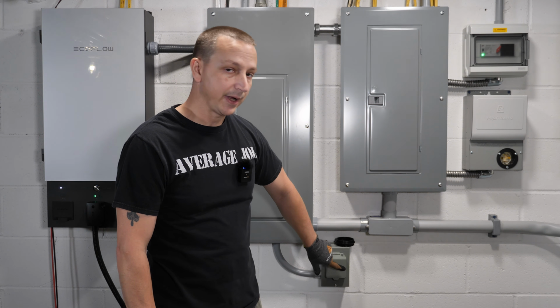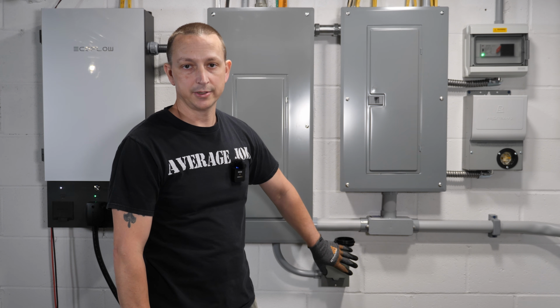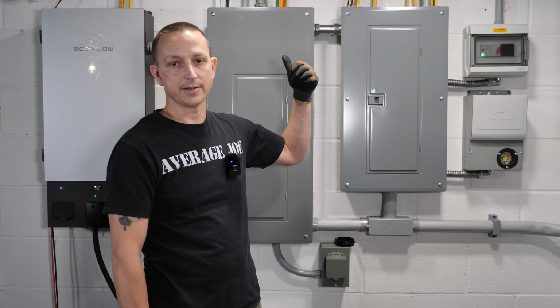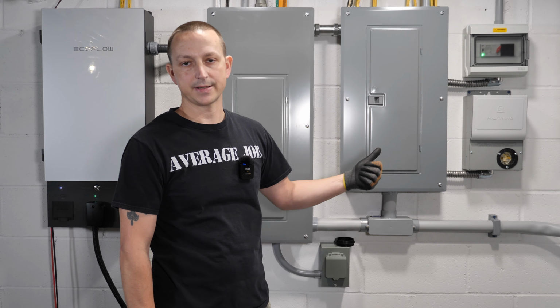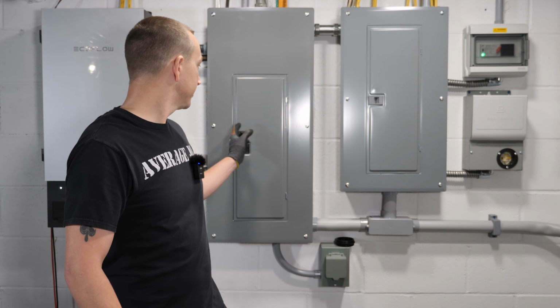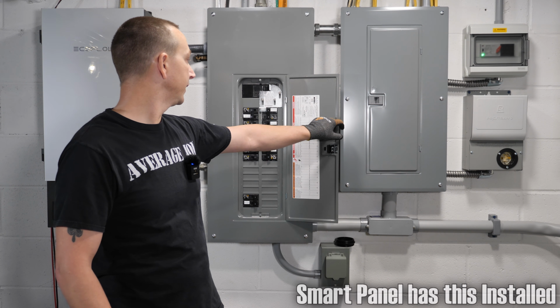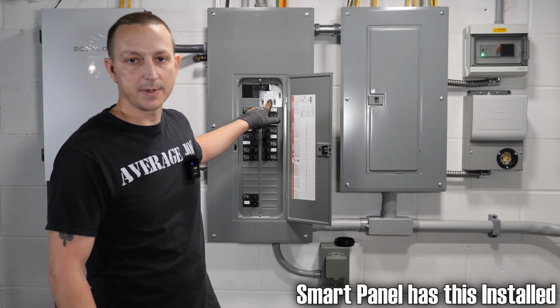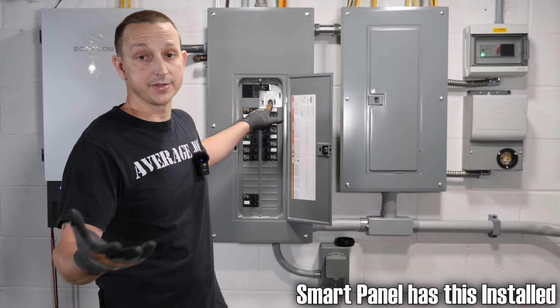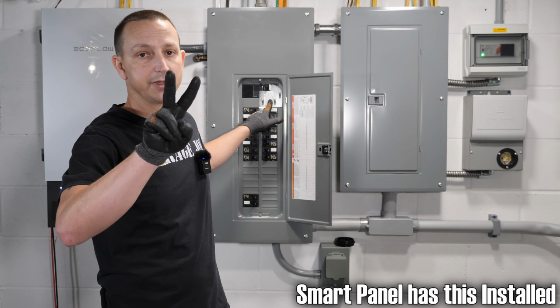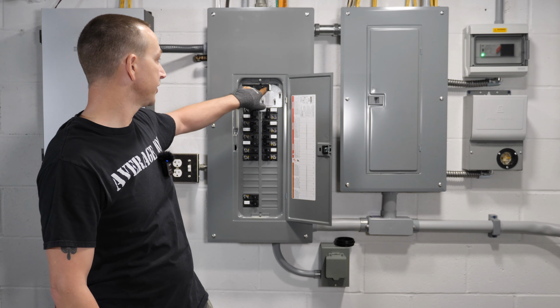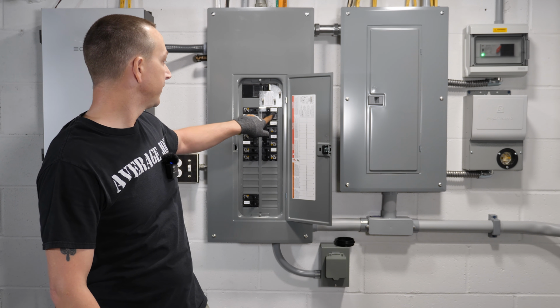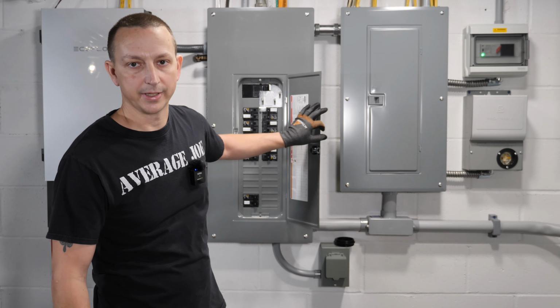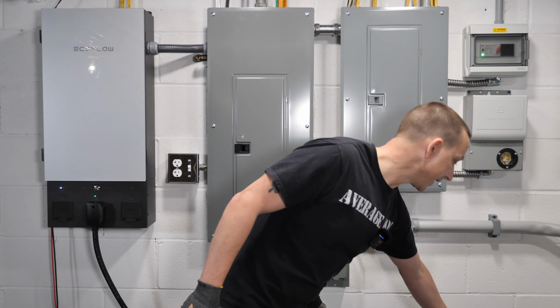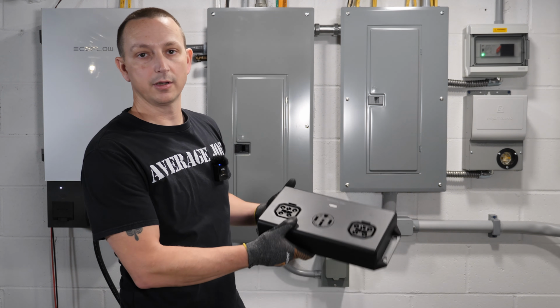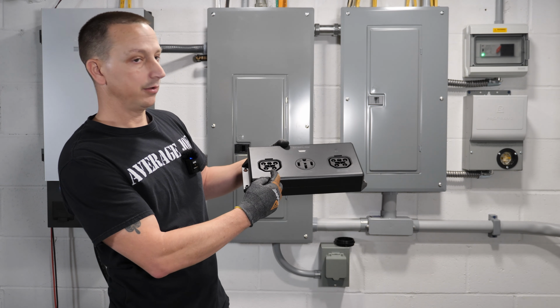Number 2 is going through a 50 amp generator plug. Typically you would have something like this installed outside where you would connect up a gas or diesel generator. And whenever you use that, you also need a generator lockout right here. This basically prevents you from powering your house or the grid from 2 different sources. You have to shut off your main, lift the switch up, and then turn on your generator breaker.